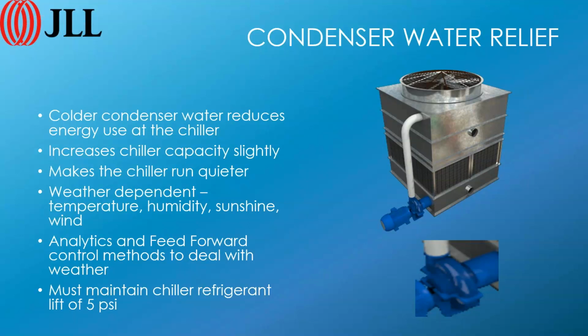There are some temperature conditions or weather conditions you have to be concerned about: temperature, humidity and sunshine. The way that we deal with that is that we look at the energy use of the chiller plant. So the total energy use of the plant, the chiller, the condenser pumps, and the cooling tower all together, we add that all up, and we record that. The BMS records that and keeps it in its memory, and then it drops the temperature of the condenser water down by 1 degree, and waits about 15 minutes for everything else to settle out, all the steel and whatever else is in the system to reach equilibrium, and then measures the total power plant use again.